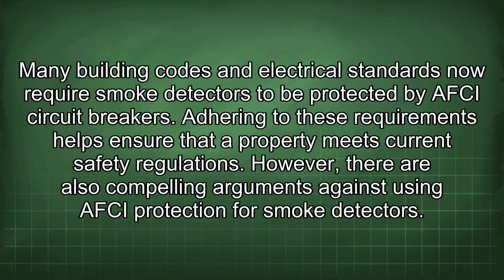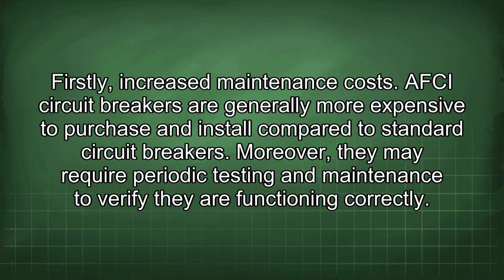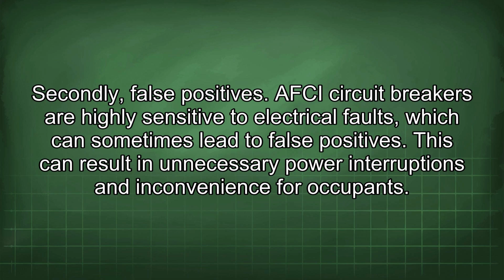However, there are also compelling arguments against using AFCI protection for smoke detectors. Firstly, increased maintenance costs. AFCI circuit breakers are generally more expensive to purchase and install compared to standard circuit breakers. Moreover, they may require periodic testing and maintenance to verify they are functioning correctly. Secondly, false positives. AFCI circuit breakers are highly sensitive to electrical faults, which can sometimes lead to false positives. This can result in unnecessary power interruptions and inconvenience for occupants.